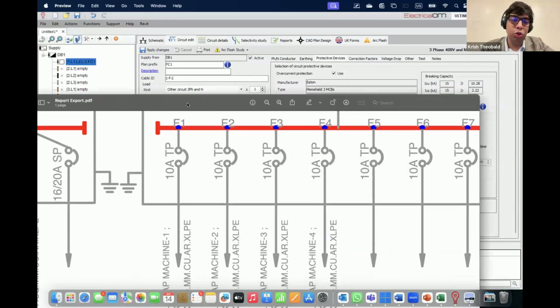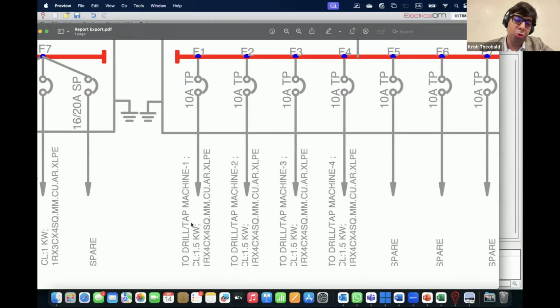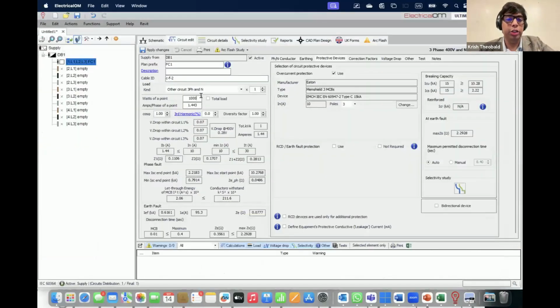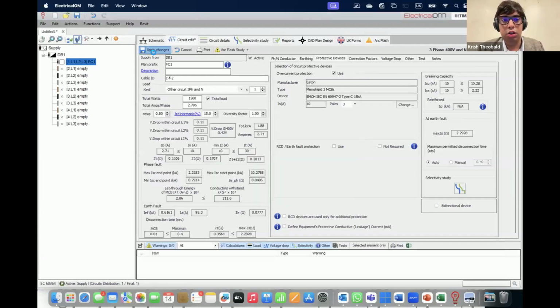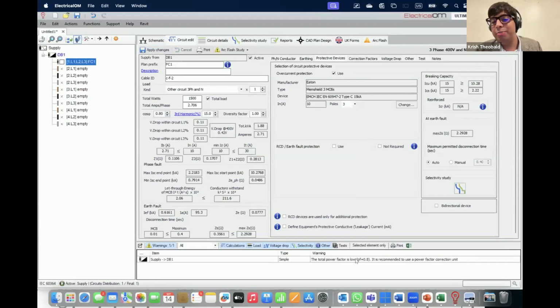What is our actual load? So this tells us that we want it to be 1.5 kilowatts. So I will enter here 1.5 kilowatts. Say I have a power factor of 0.8, static, but okay. Total load, and say I have a third harmonic value of 15%.